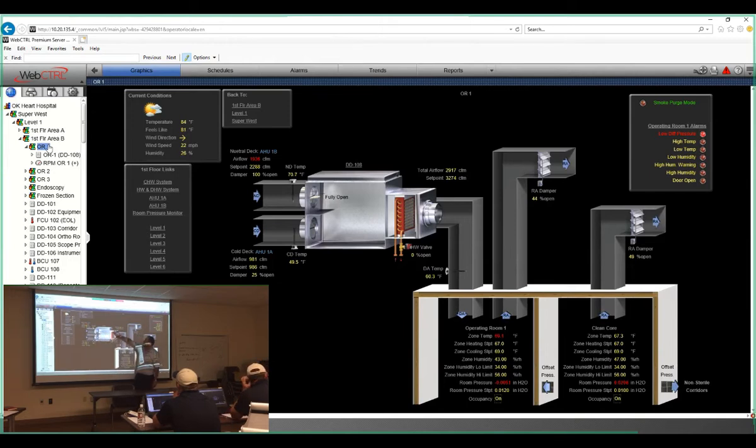So this is going to try to maintain the 3275, and then the return damper, which is just a normal return going back to the unit, is going to try to maintain this room pressure set point of 0.012. We bumped these up this last week to make sure we don't fall below when things change and doors open and all that. The goal is 0.01. The set point on some of these right now is 0.012.